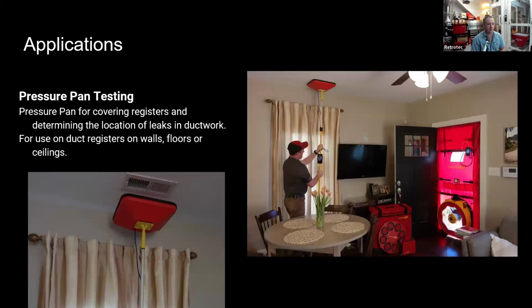I see this manometer as a great sidekick for your blower door. So you can attach this to a pressure pan if you're running a blower door test to depressurize the house to negative 50 pascals. Then you can attach this gauge to a pressure pan and then run around and look for leaks, just like you would with an extra DM32 or a DM32X, except for now you just don't have to have that additional expensive manometer. This is just a little sidekick that'll do the same thing at a lower cost for you. So whether you're looking for duct leakage in supplies or returns, or if you're looking for envelope leakage, like maybe to see how much can lights are leaking or covering outlets or light switch covers and things like that, you can do that the exact same way that you have been with your other manometers that you're used to.